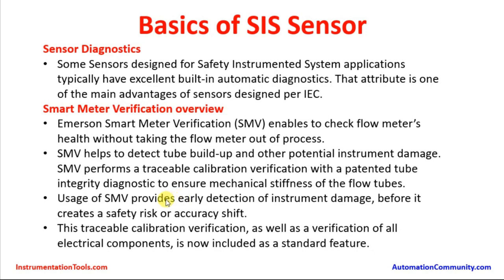Usage of SMV provides early detection of instrument damage before it creates a safety risk or accuracy shift. As stated, reliability of the instrument should be very high whenever used in a safety instrumented system application. SMV helps make early detection because it is always performing self-diagnostics. Traceable calibration verification as well as verification of all electrical components is included as a standard feature — this covers verification of the flow tubes as well as the electronics available in the sensor.